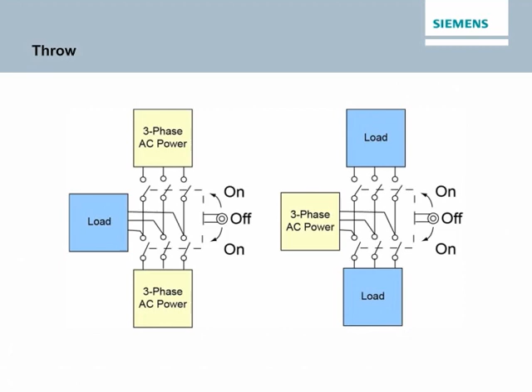For example, the accompanying illustration shows 3-pole non-fusible safety switches. For either of the 2 applications, no power is applied to a load with the switch in the center, which is the off position, and only one set of contacts can be closed at a time. In the application on the left, with the switch in the up position, the upper power source is connected to the load. With the switch in the down position, the lower power source is connected to the load. In the application on the right, with the switch in the up position, the power source is connected to the upper load, and with the switch in the down position, the power source is connected to the lower load.